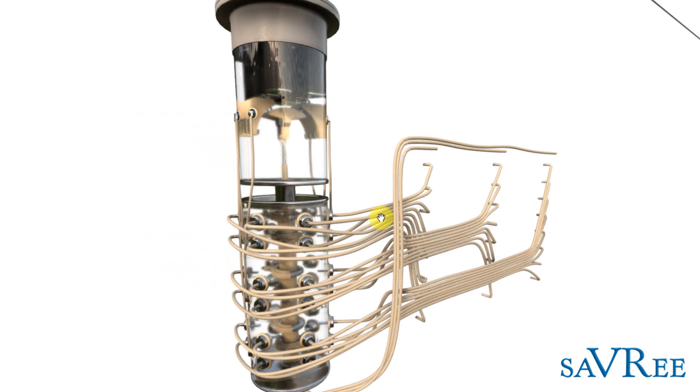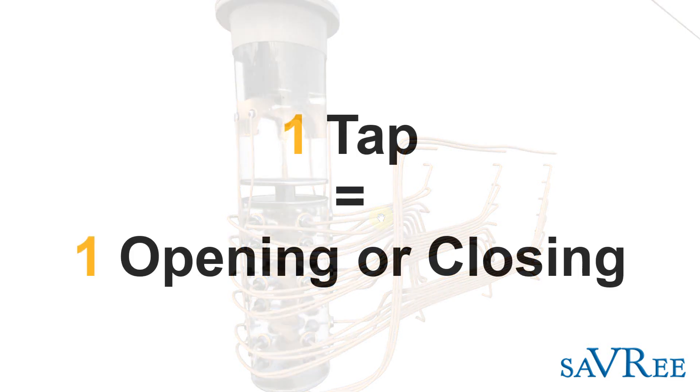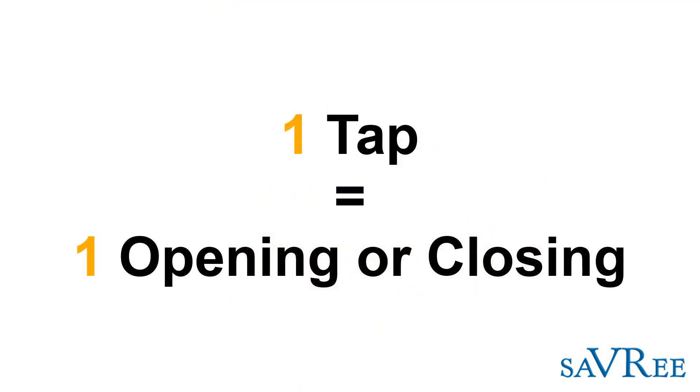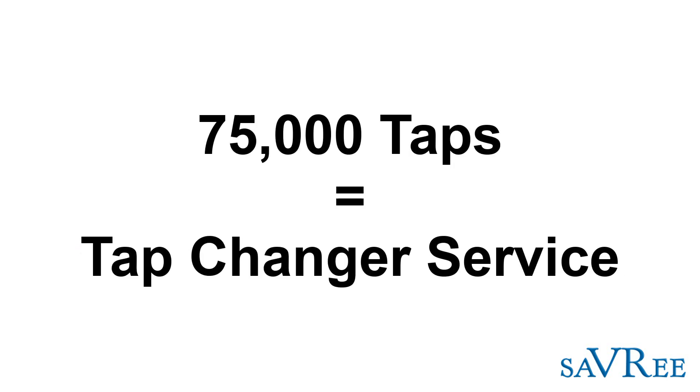Typically, when you're looking at a tap changer, the thing that you need to pay attention to is the number of taps. The number of taps are typically used to indicate when the unit should be maintained. And a typical number like 70,000 taps would indicate that it's time to take the tap changer out and service it.